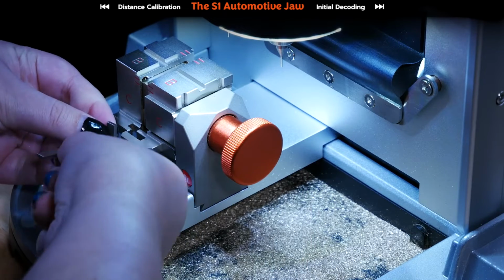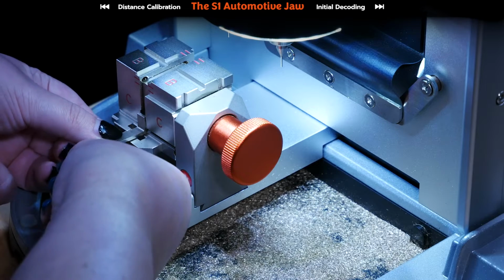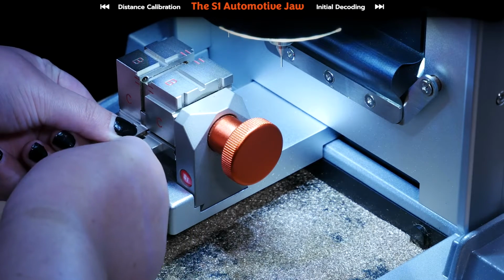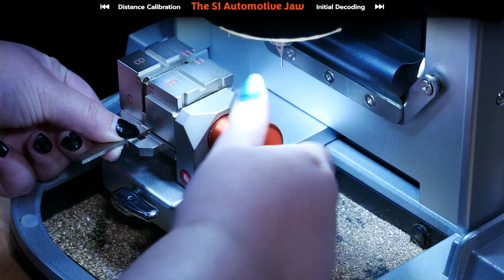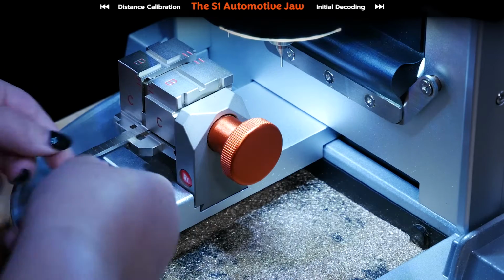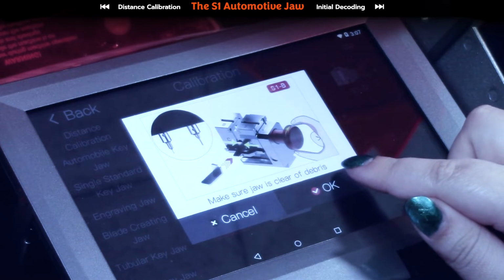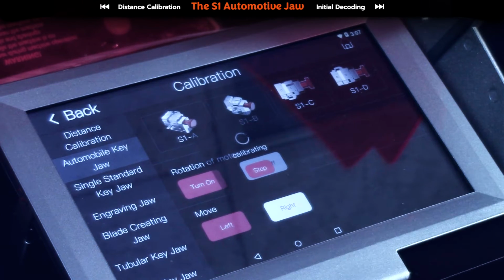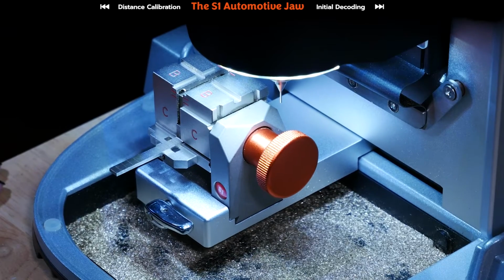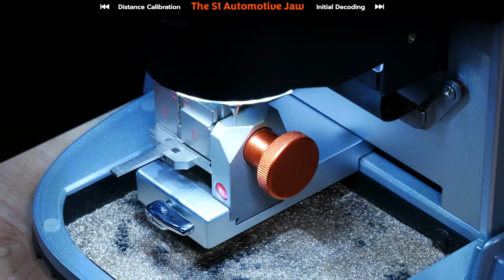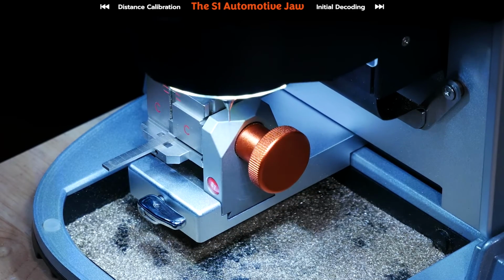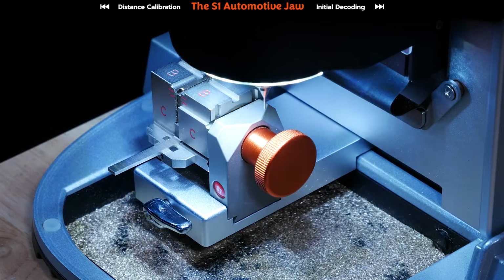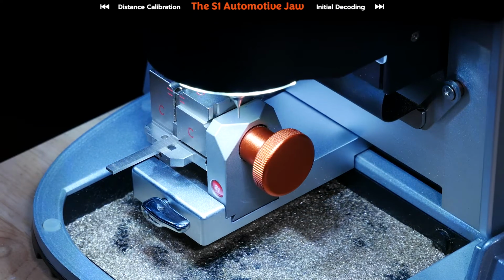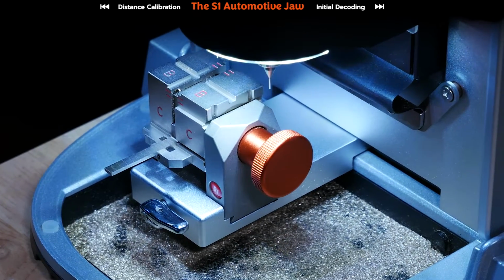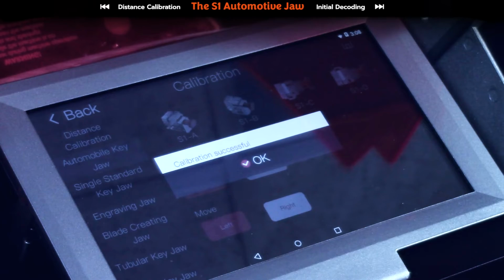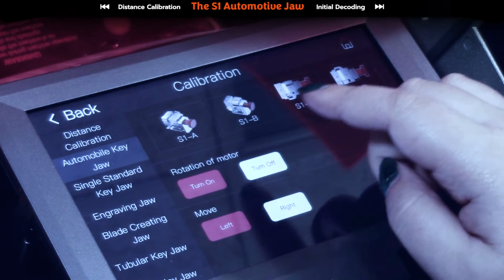So long end pointing outwards, short end pointing up. And you're going to put it in at the very bottom, resting up against this ledge here, and push it all the way in until it can't go in anymore. Tighten up the orange knob, secure it in place, can't move, good to go. Hit OK to start the calibration. Calibration successful, hit OK on the screen, and now we're going to go over to S1A.